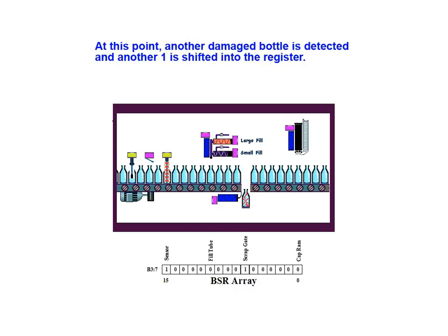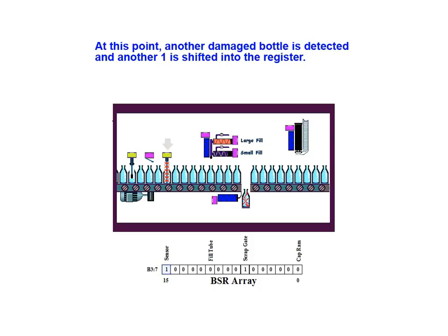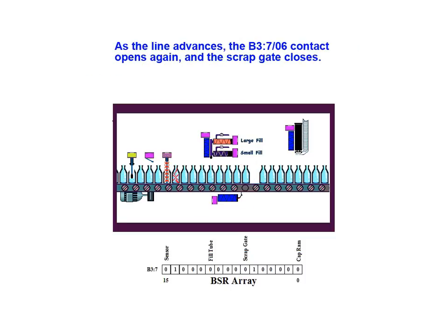At this point another damaged bottle is detected and another 1 is shifted into the register. In addition, a normally open contact having address B3:7/06 is located on the scrap gate rung, and as the contact closes the gate opens, dropping the scrap bottle. As the line advances, the B3:7/06 normally open contact opens again and the scrap gate is closed.